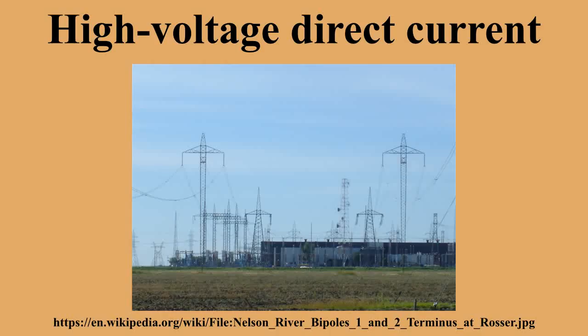For an 8 GW 40 km link laid under the English Channel, the following are approximate primary equipment costs for a 2000 MW 500 kV bipolar conventional HVDC link: converter stations, £110 million; subsea cable plus installation, £1 million per kilometre. So for an 8 GW capacity between England and France in 4 links, little is left over from £750 million for the installed works. Add another £200 to £300 million for the other works depending on additional onshore works required. An April 2010 announcement for a 2000 MW 64 km line between Spain and France is estimated at €700 million. This includes the cost of a tunnel through the Pyrenees.